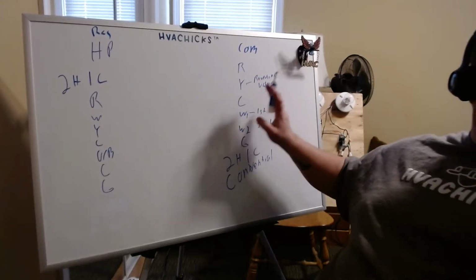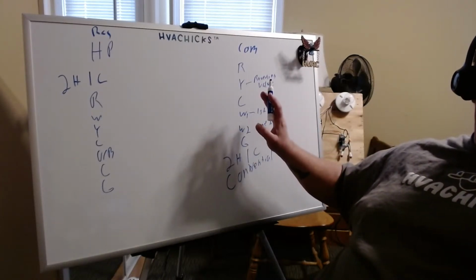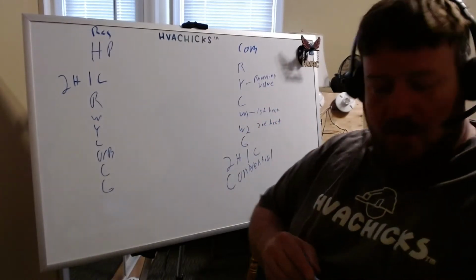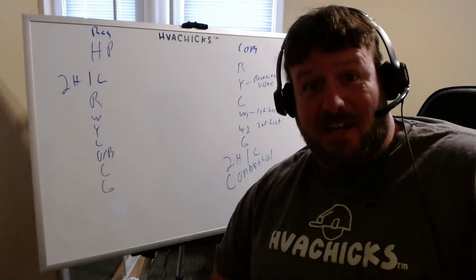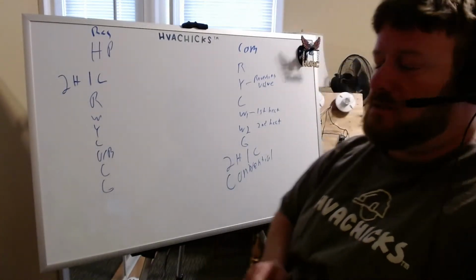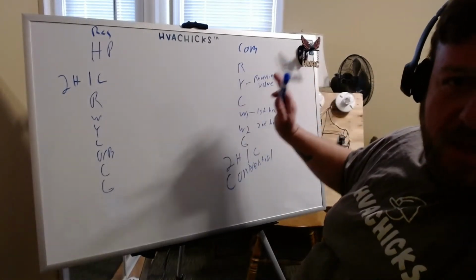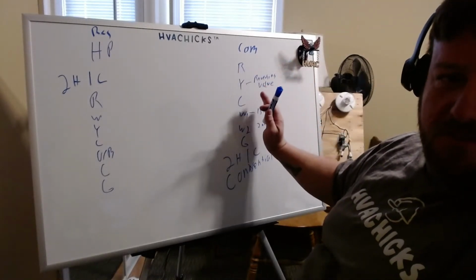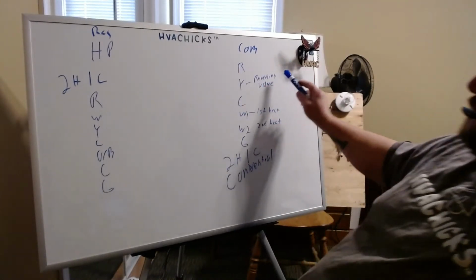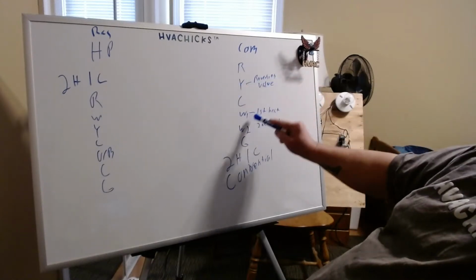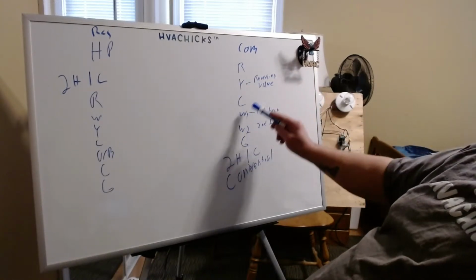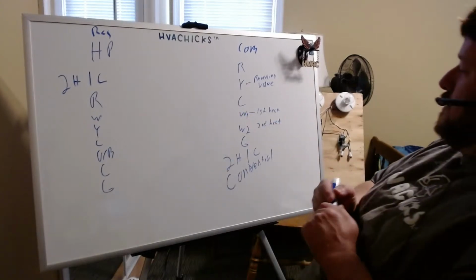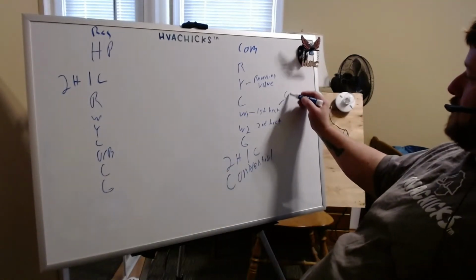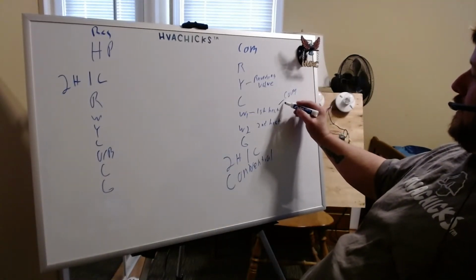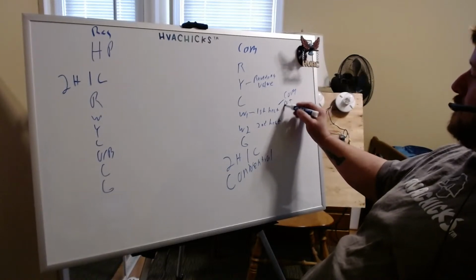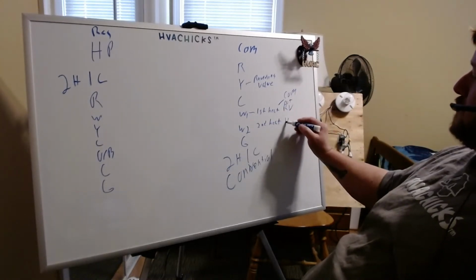So like you'd wire this up as a gas furnace. Okay. That being said, yes, I did say that. You wire it up as a gas furnace because that is how the controls on these type systems are done. They energize the reversing valve when Y is called and no call for W. When you get a call for W, this will energize your compressor and not the reversing valve. This will energize your heat strips.